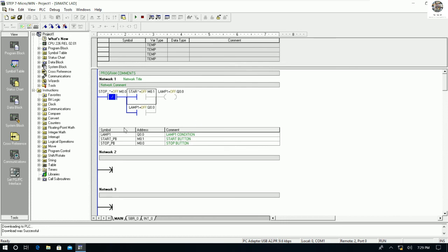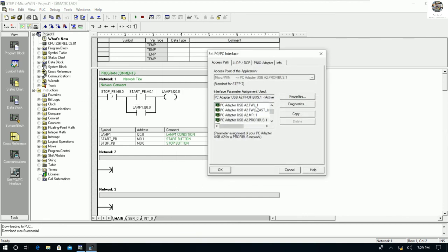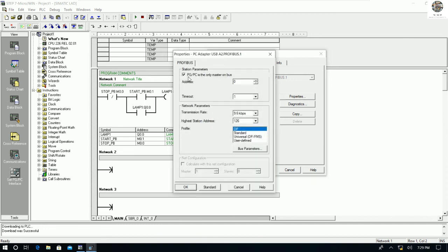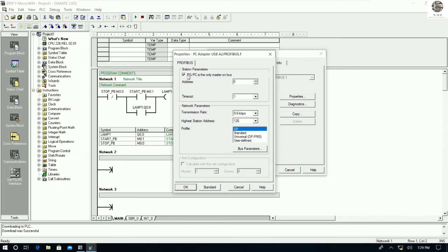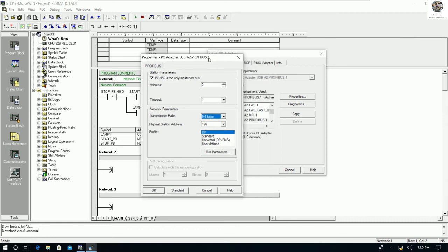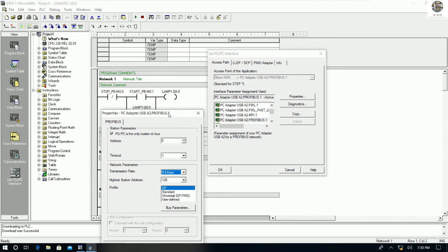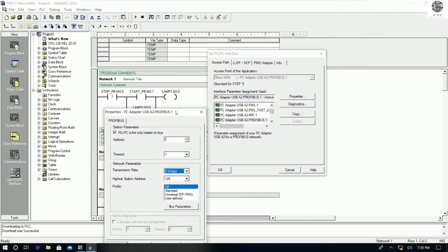Don't forget to set the PG/PC interface; otherwise we cannot communicate between our PC and the PLC. Choose PC Adapter USB A2 Profibus, go to Properties, check the checkbox, and choose 9.6 kbps for the baud rate. Thank you very much for watching. If you have any questions, please drop a comment under my video and I will reply soon. Please like, share, and subscribe to get notifications about new videos.